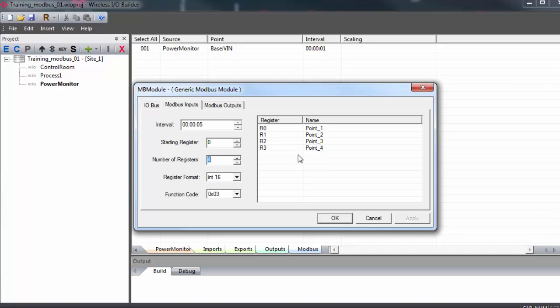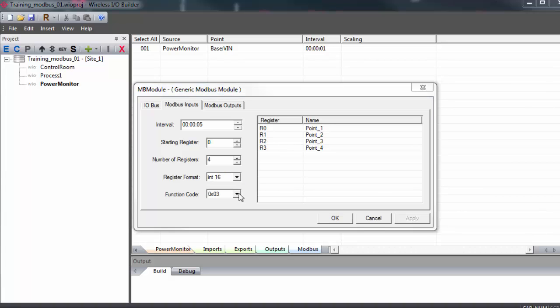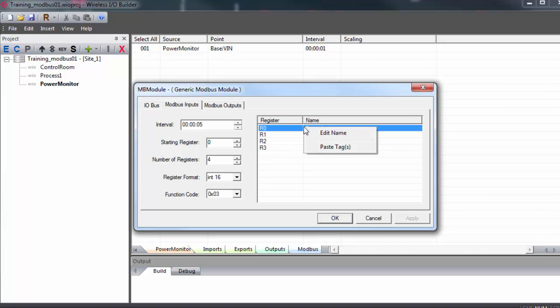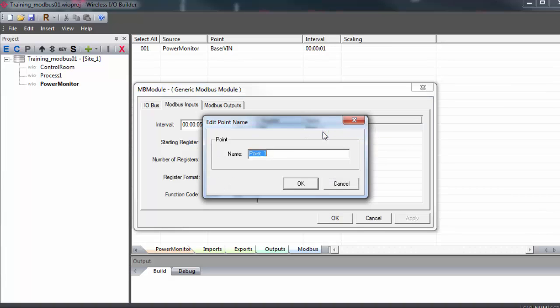I'll start writing at address 0 and I'll write 4 registers. Values must be written as either 16 or 32-bit holding registers. The wireless I.O. gateways support function codes 3, 4, and 6. And for each point that we have, you can right-click, edit, and give the register a name.